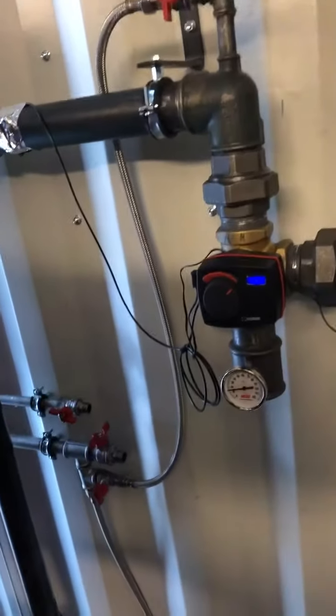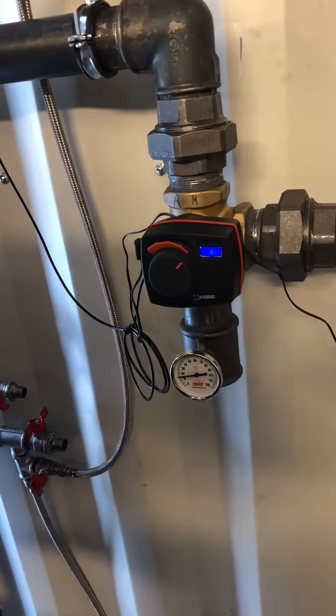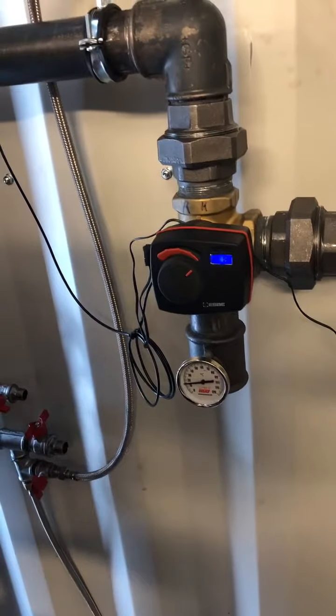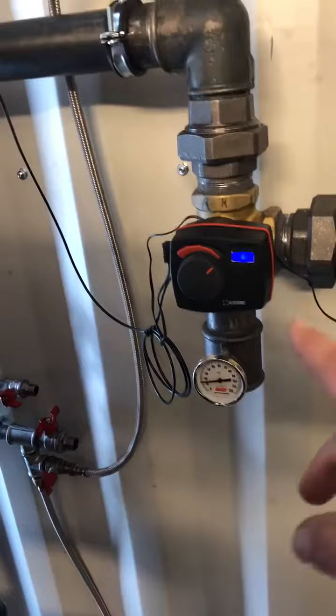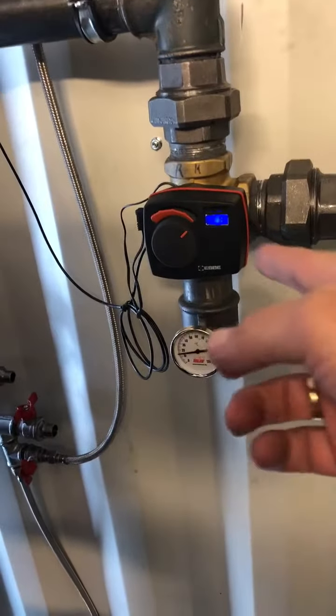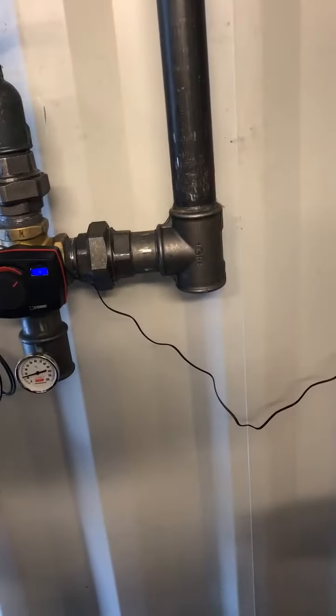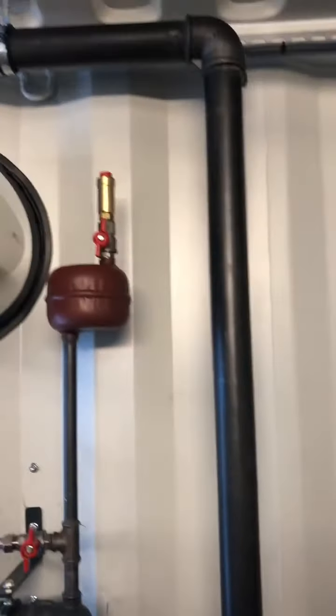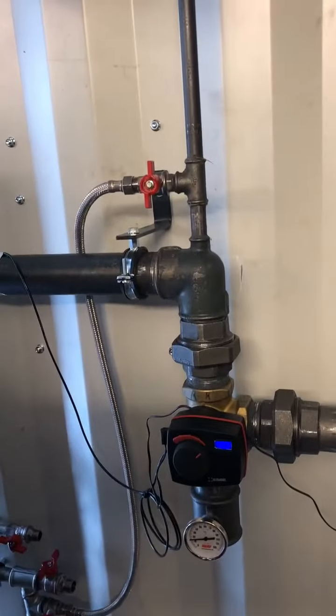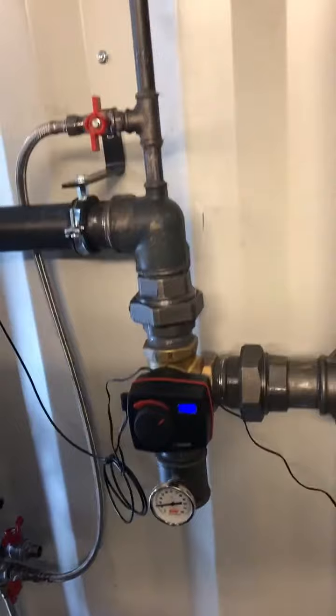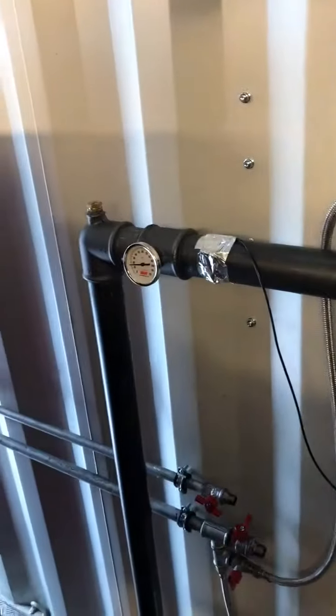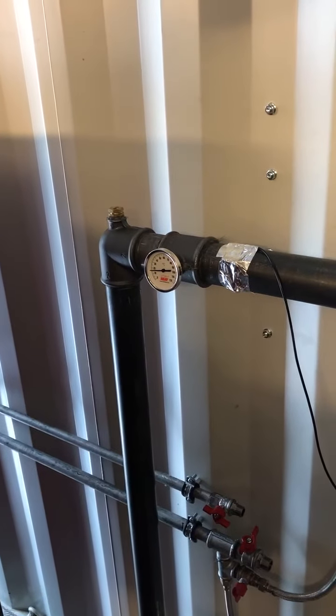Over here on the wall we have the shunt valve, electrical regulated motor valve, and it's always placed on return line. So this is the return, the cold water coming back to the system, and this is a forward line going away from the boiler. And we always want 60 degree in return temperature. So we are over the compensate point. And you can always adjust that after that temperature gauge placed there on return pipe.